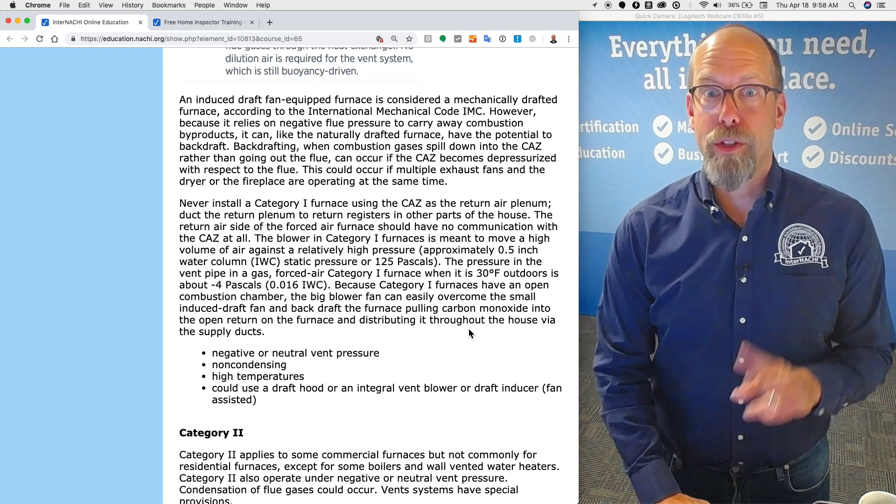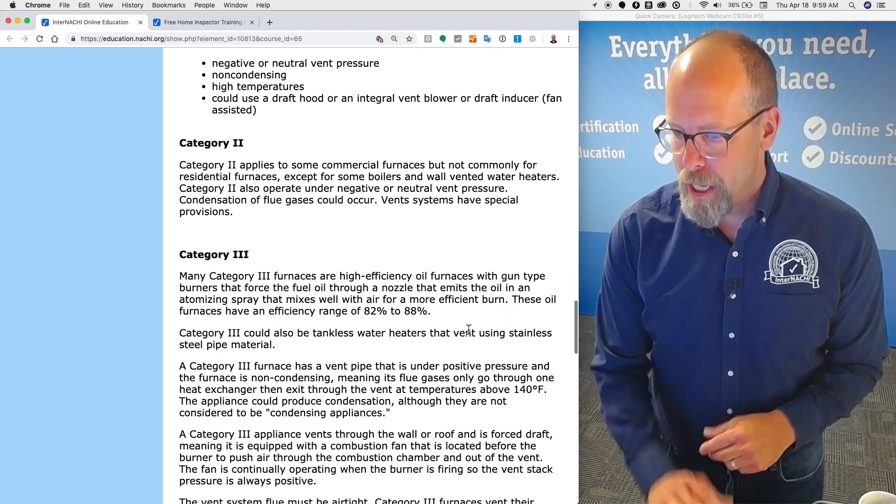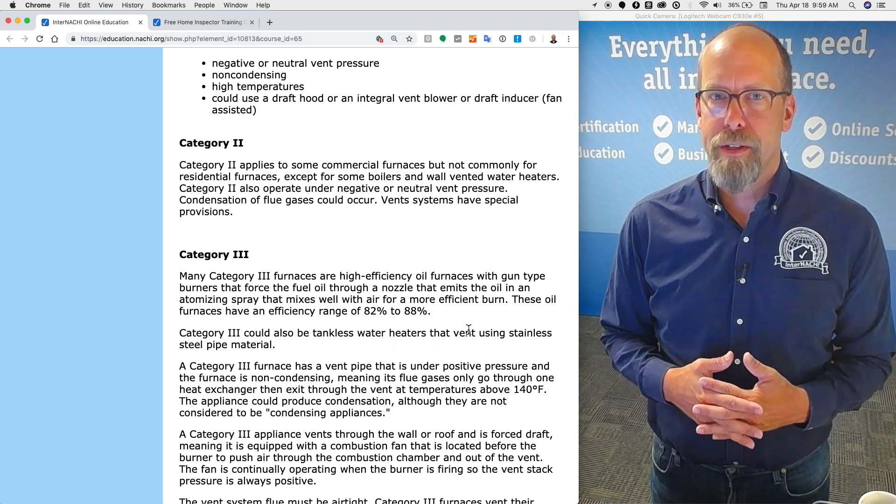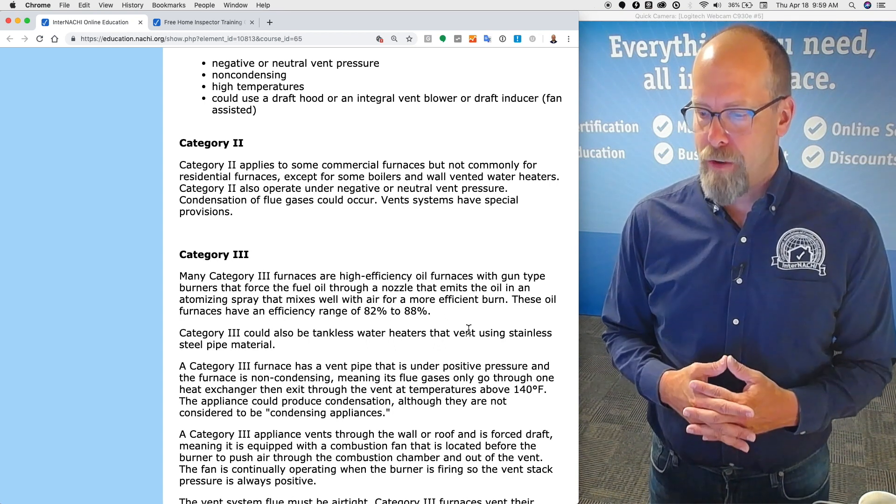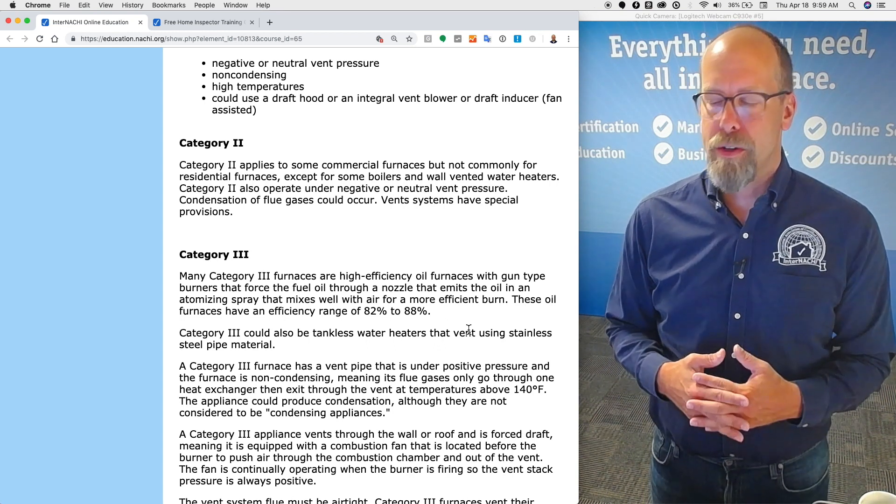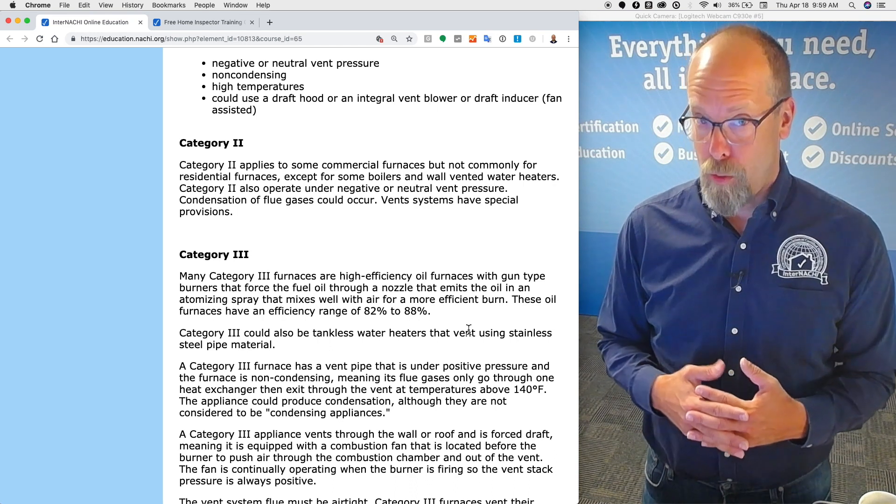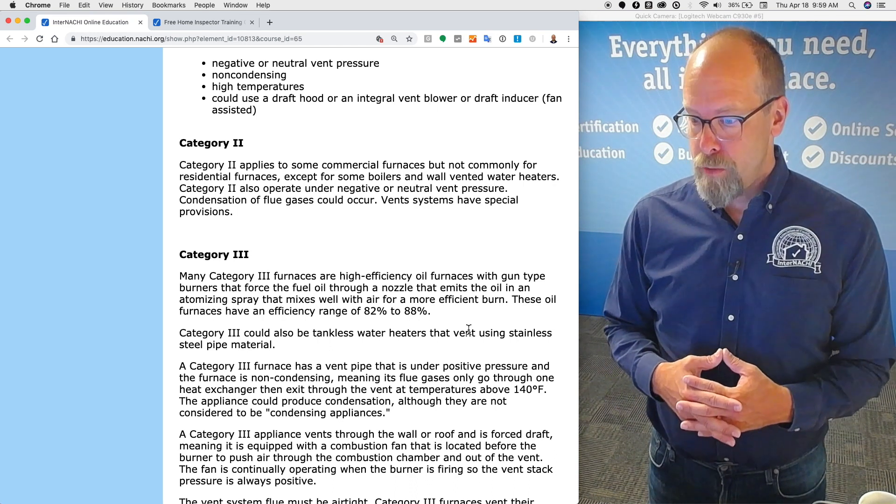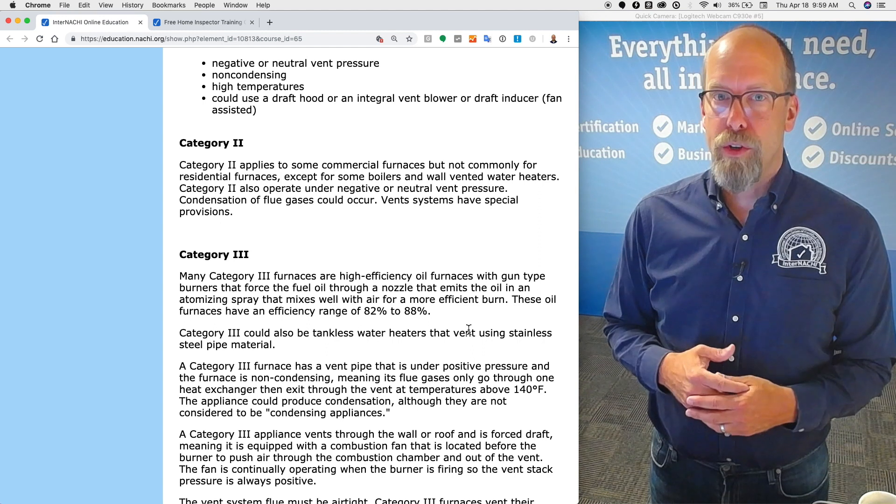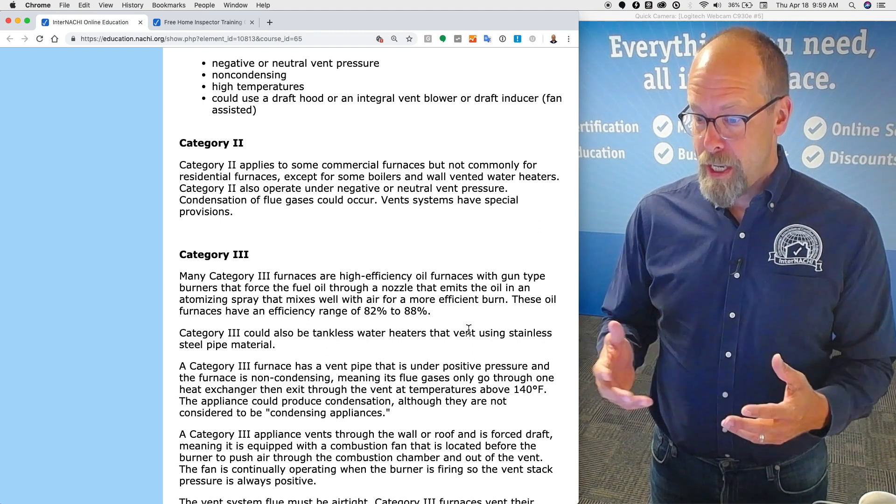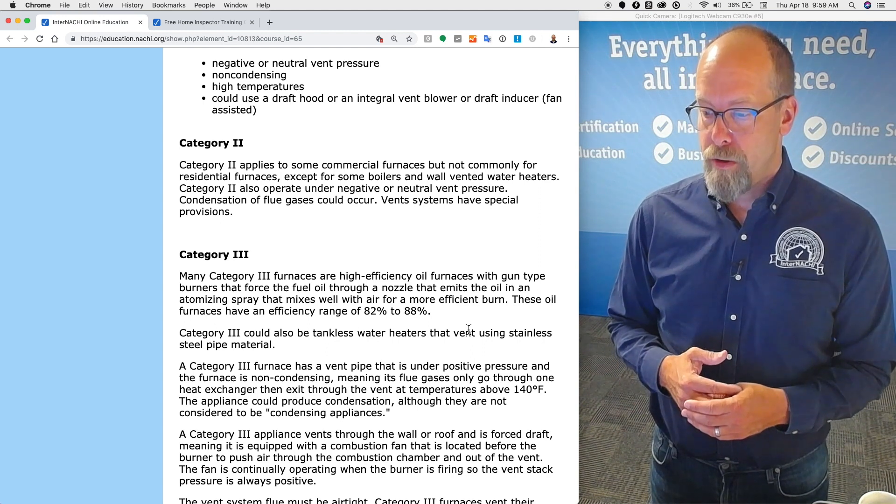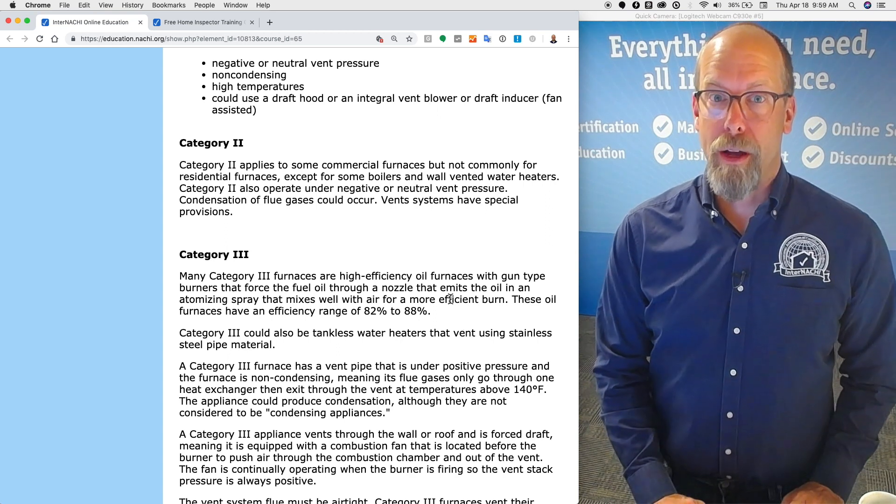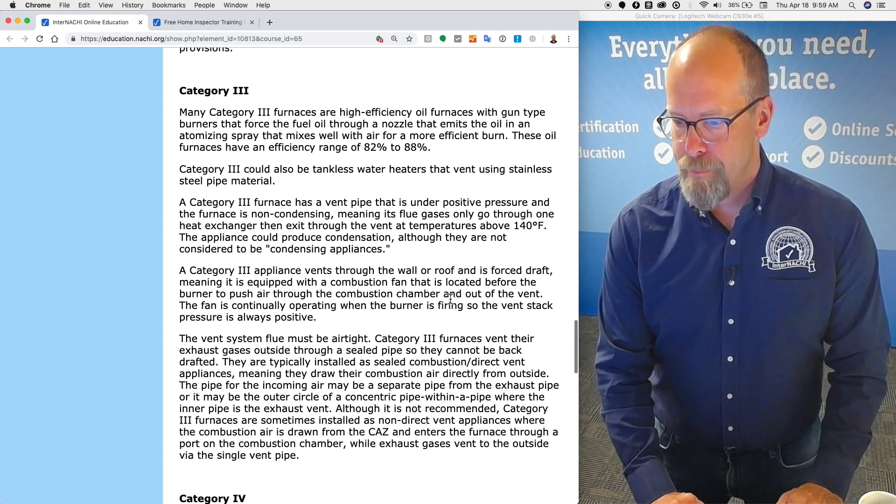Category two furnace or appliance. Category two applies to some commercial furnaces and not commonly for residential furnaces except for some boilers and wall vented water heaters. Category two also operates under negative or neutral vent pressure. Condensation of the flue gases could occur. Vent systems have special provisions from the manufacturer.